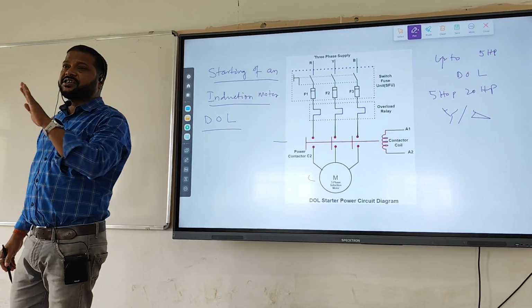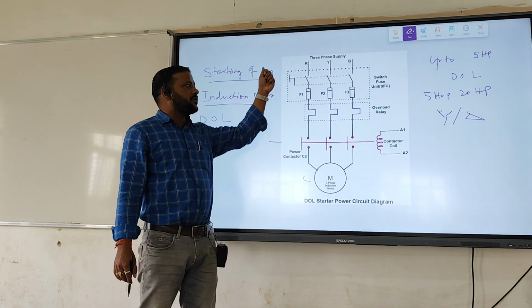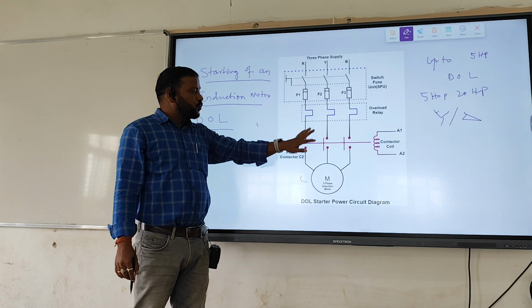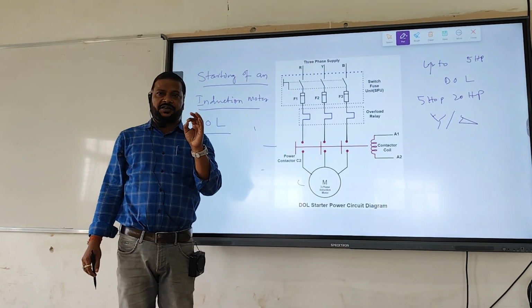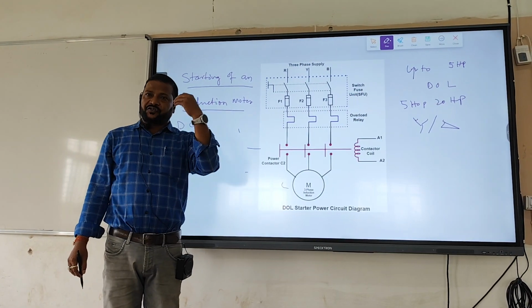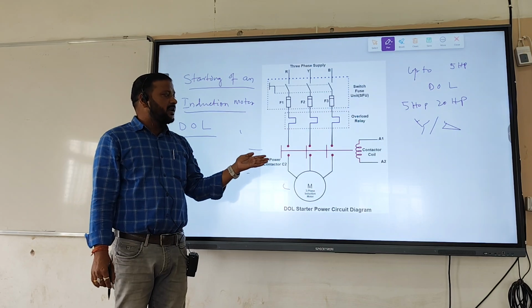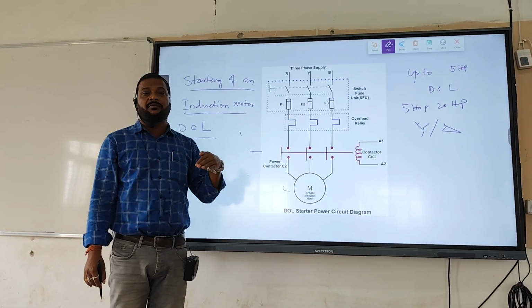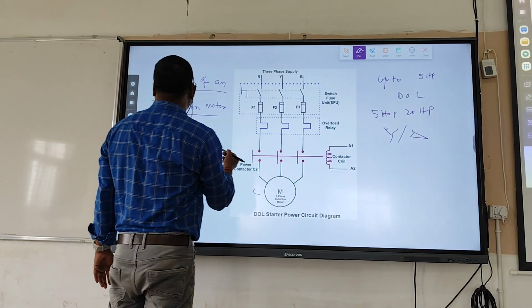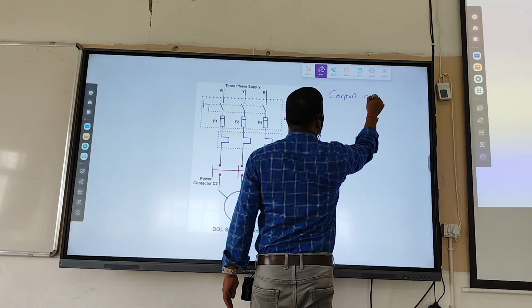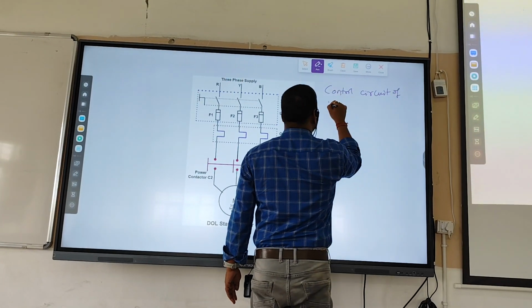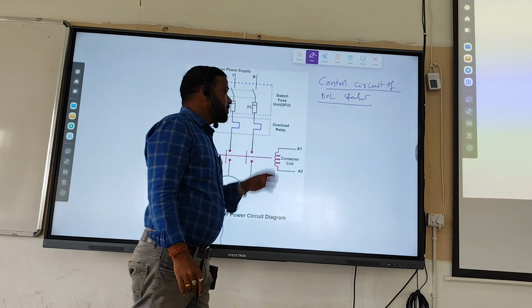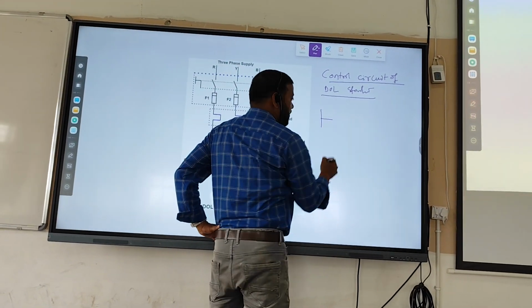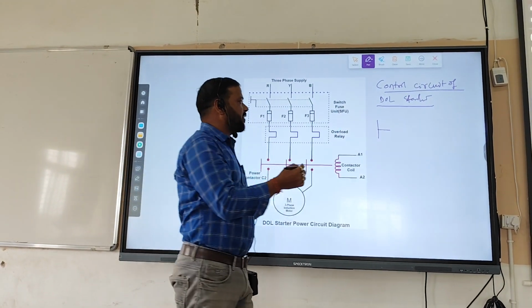But the contactor coil will not switch on by itself, although we switched on the fuse and the TPSP switch. To safely energize the contactor, one control circuit is mandatory, through which we can safely flow the current towards the contactor, so that the contactor can energize, allow the current to flow, and the motor can start safely. Now let me draw the control diagram of this starter. I will show you the control part of this starter through a one line diagram.